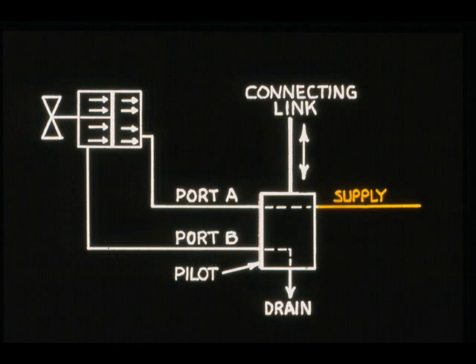To open the valve, port B is connected to the supply. Port A is connected to the drain. To close the valve, port A is connected to supply. Port B is connected to the drain.